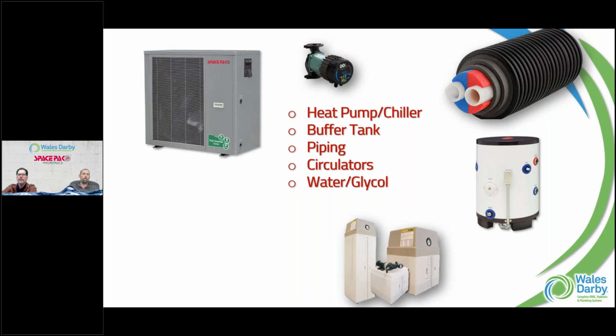But in our region, we have some considerations there too when we start moving chilled water versus hot water, and then now you have 15 to 20% glycol. Been on jobs where we cracked a valve, purge valve, and gotten bright blue water, I think 100% concentrate. Lose a lot of BTUs, you got to pump harder, all of that fun stuff. So we need to understand that.